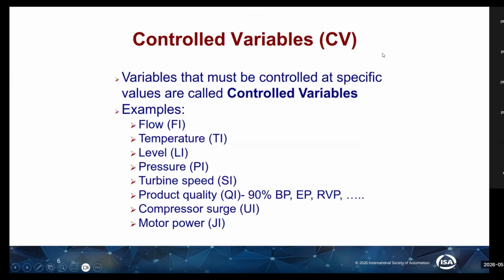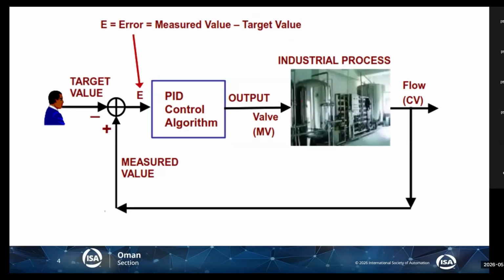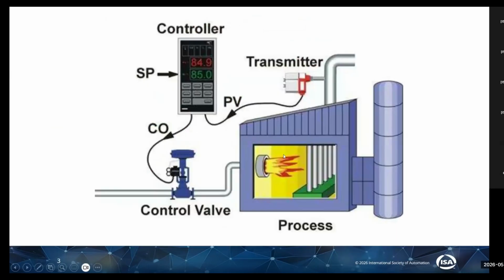Some of the terminologies that we need to understand: the CV, which is the controlled variable. If we go back to the previous example, our controlled variable is the temperature, which is produced as a result of burning this fuel gas. Our MV, which is our manipulated variable, is our control valve. So the controller is controlling the controlled variable, temperature, by manipulating the control valve.